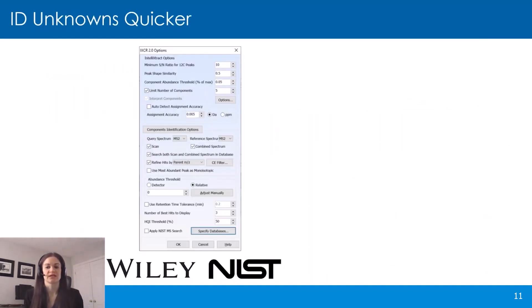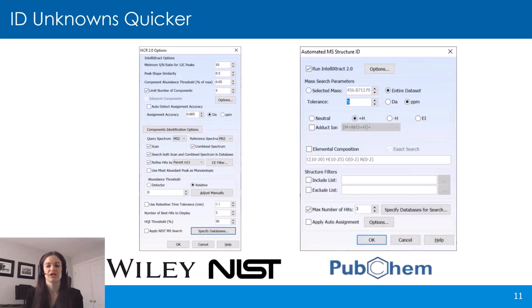Regarding searching databases, we have a few tools for this. One tool is called IXCR, which will do the componentization and search databases by spectra. It can search commercially available databases such as the Wiley databases or in-house user-created databases, and give you an HQI — a hit quality index value — for the hits that are found. You can also use the NIST MS search algorithm as part of this and search the NIST database. Alternatively, you can search PubChem, which contains more than 100 million structures, and you can do this search by mass or elemental composition. You can include or exclude lists to help narrow down those hits. The results would be a table of structures and a formula fit quality or FFQ score. You can also choose to run the in silico fragmentation as part of this to get the spectrum assignment score mentioned previously.